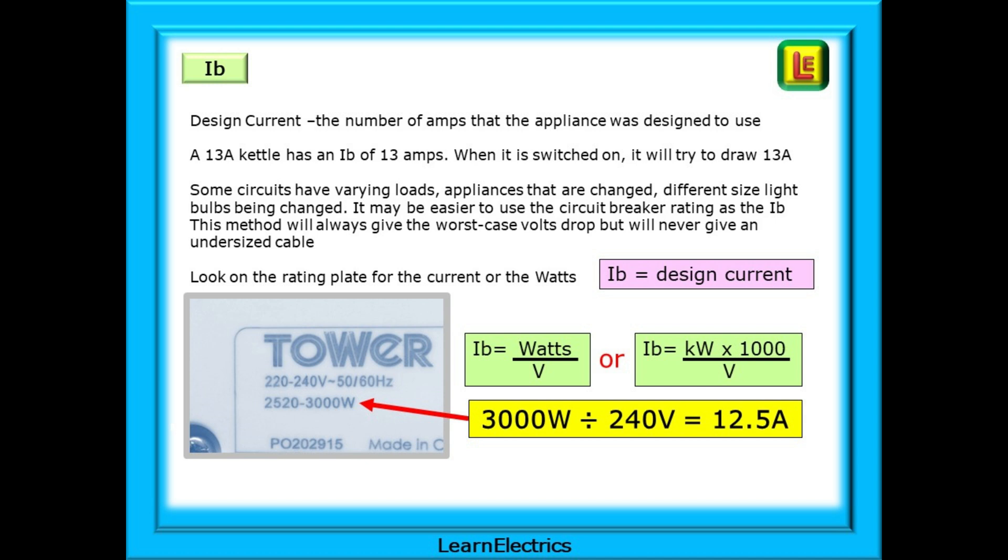IB is the design current, the number of amps that the appliance was designed to use. A 13 amp kettle has an IB of 13 amps. When it's switched on, it will try to draw 13 amps. Some circuits have varying loads or appliances that have changed, different sized light bulbs being changed. It may be easier to use the circuit breaker rating as the IB. This method will always give the worst case volts drop but will never give an undersized cable. Look on the rating plate for the current or the watts.